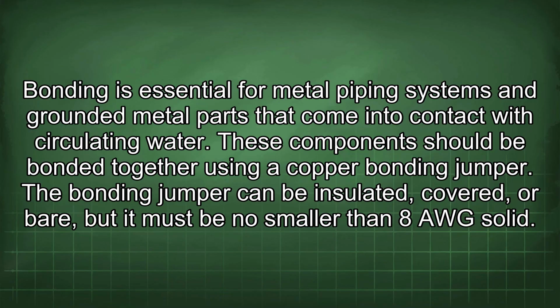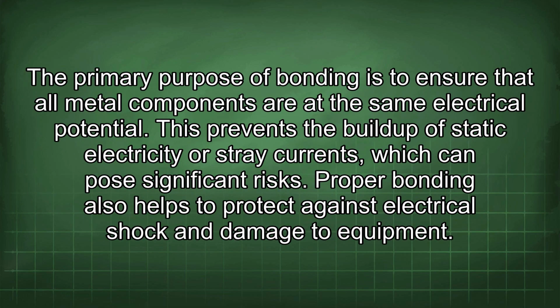Bonding is essential for metal piping systems and grounded metal parts that come into contact with circulating water. These components should be bonded together using a copper bonding jumper. The bonding jumper can be insulated, covered, or bare, but it must be no smaller than 8 AWG solid. The primary purpose of bonding is to ensure that all metal components are at the same electrical potential.